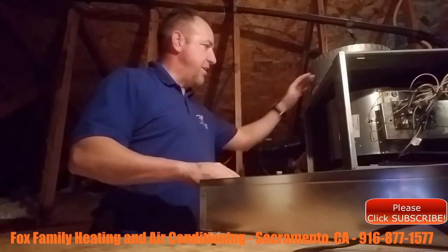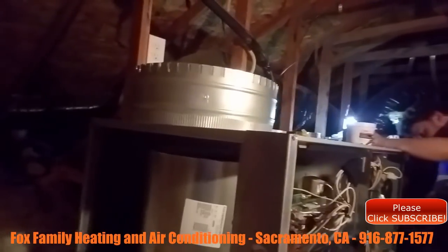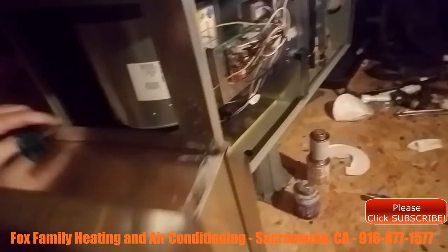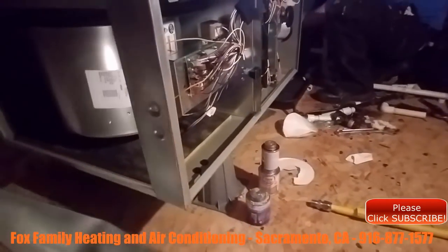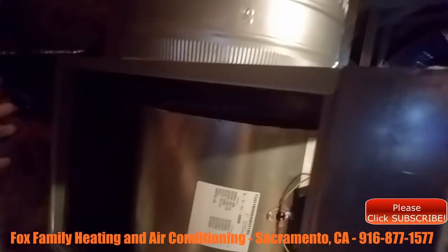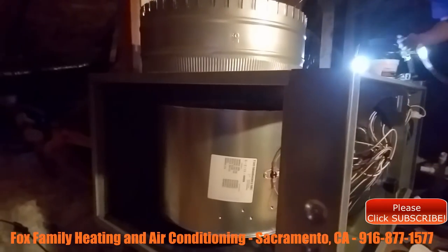Okay, so at the end of this furnace, we have an opening here. So we're going to put this return air can on there with this collar, and then we're going to hook the ductwork up to it. This return air can is 3 or 4 inches deep. Once it's on there, that's going to give the duct enough room to come in and spread itself out enough so that the air can get into the blower efficiently. So that's the goal there.